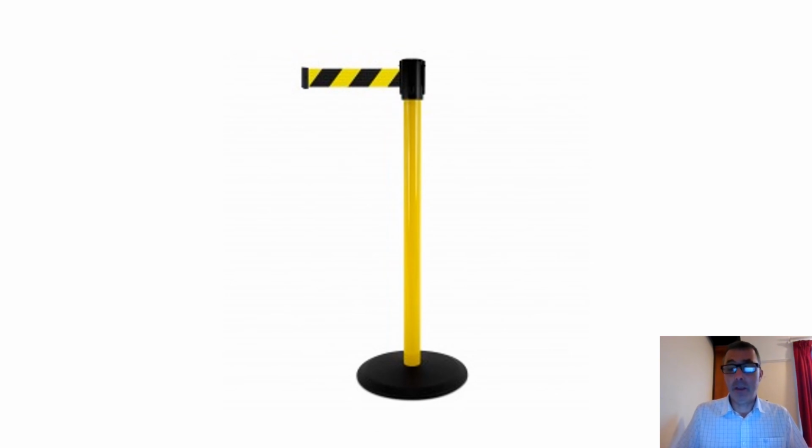So if you haven't got a magnetic lock on the door, you may have a physical lock, and in situations where the theatre are insistent that they can't have a lock on the door, you can use signs and lights and some kind of physical barrier across the door, which will really stop people from entering the laser room, controlled area, or the theatre during a laser session.